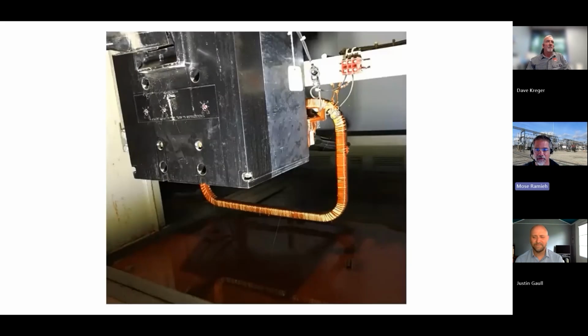that ring, that kind of reddish gold ring that everybody can see behind the black circuit breaker, is a zero sequence CT that's there for ground fault protection on this circuit. And the red goo that's now in the bottom of the gear is what used to encase those turns of wire that create the CT. And this is a very common problem on ITE switchgear.